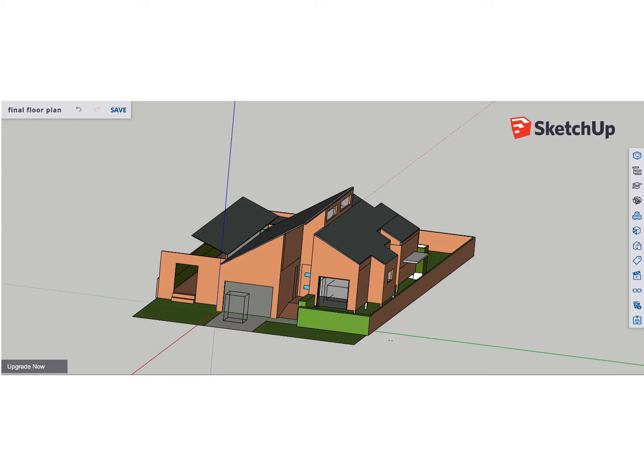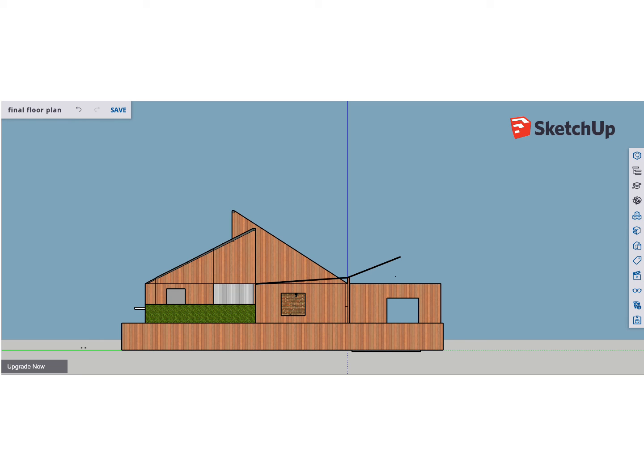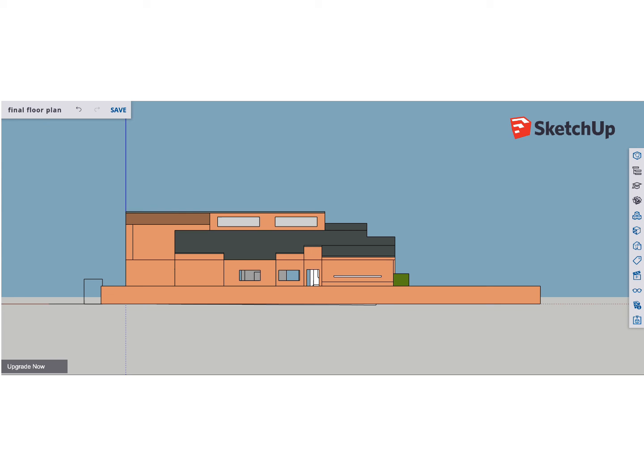For the windows, we will be using a 4x12x4 clear argon low-e double-glazed pane. This will provide a visible light transmittance of 75%, a U-value of 1.6, and a solar heat gain coefficient of 0.64.